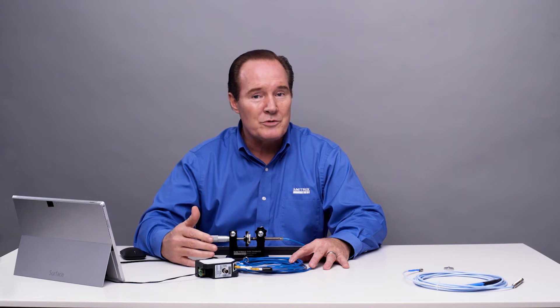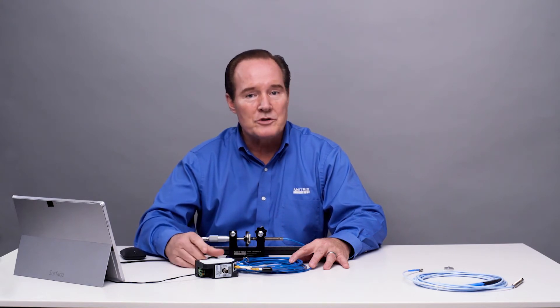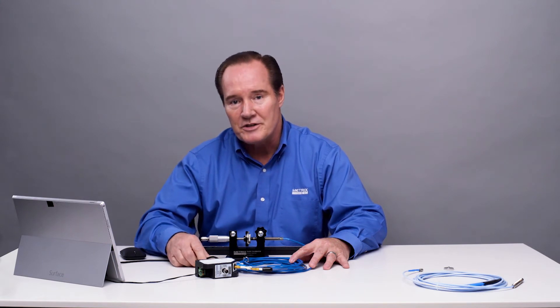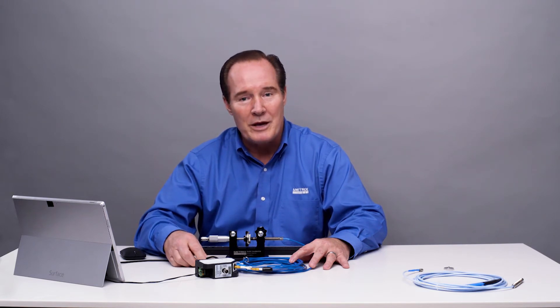We've already shown that it works with a Metrix system, so that's not a problem. Let's see if it works with the competitor's probe and cable and see if we can get a nice linear characteristic, well within the 190 to 210 millivolts per mil required from API. So let's go ahead and do that demonstration.